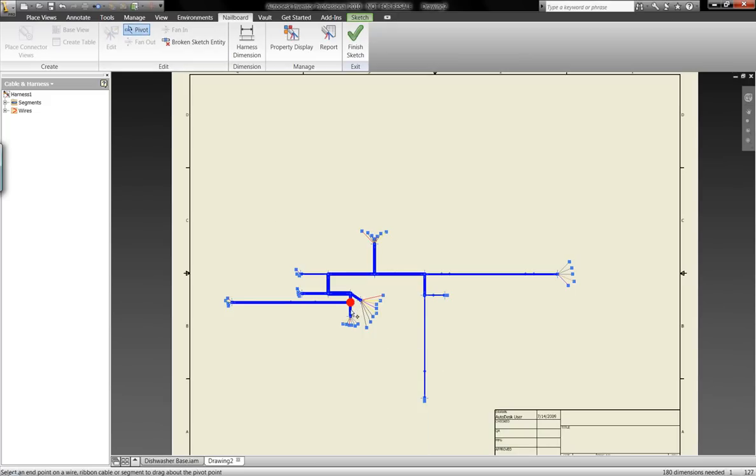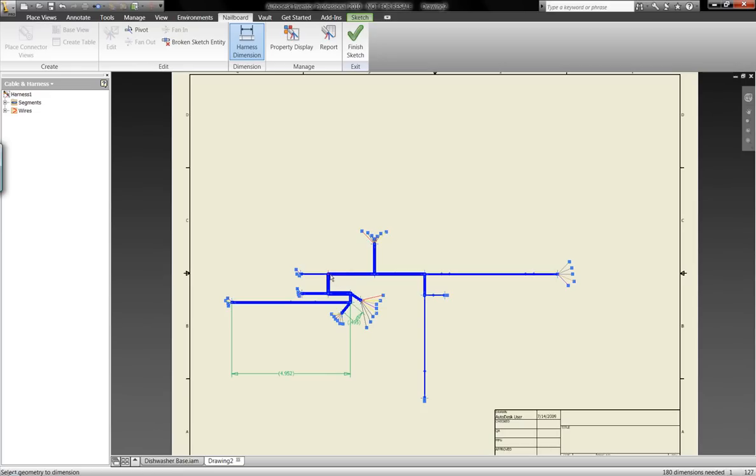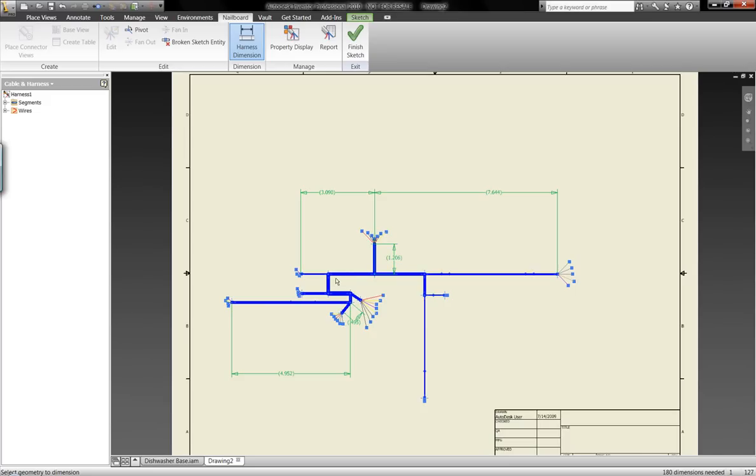Now once these components are laid off or laid out exactly as I want them, I'm now going to be able to bring in some additional information. For example, the data that is calculated from Autodesk Inventor includes things like length of the different segments. So I can dimension these different segment lengths within the nail board drawing. This is pulling the dimensional information that's created on the three dimensional model. So even though I'm looking at this in a 2D format, it's actually pulling the overall distances of wire that I need to manufacture this nail board.